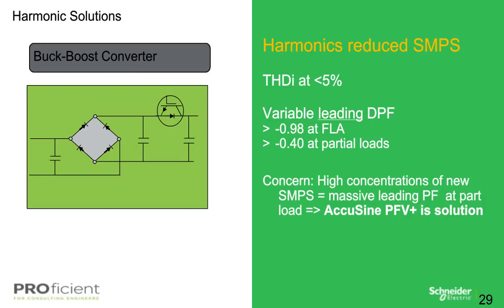However, one concern with this is that the load is reduced from FLA. The capacitor continues to inject the same leading current since it cannot flow into the switch mode power supply. It actually flows to the AC lines, thus resulting in even more leading power factor as the load drops. Then the leading DPF is treated as the same as lagging DPF by utilities and still penalized, again, based on the standards set forth by your local utility.